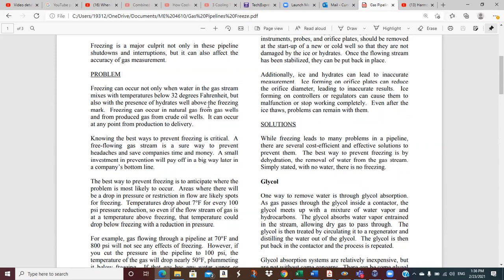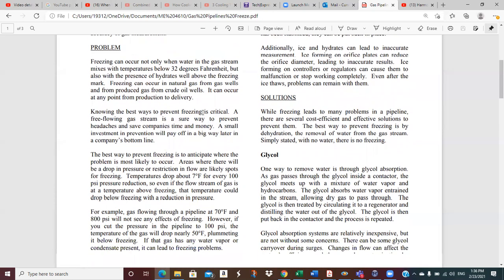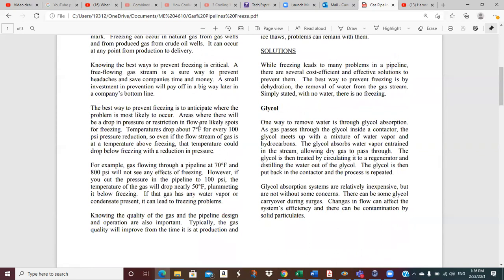Free-flowing gas stream, and so on. Let's see. Best way to prevent freeze is to anticipate where the problem is most likely to occur. They've got a little example here. Areas where there'll be a drop in pressure or restriction in flow are likely spots for freezing. Temperatures drop about 7 degrees Fahrenheit for every 100 PSI pressure reduction.